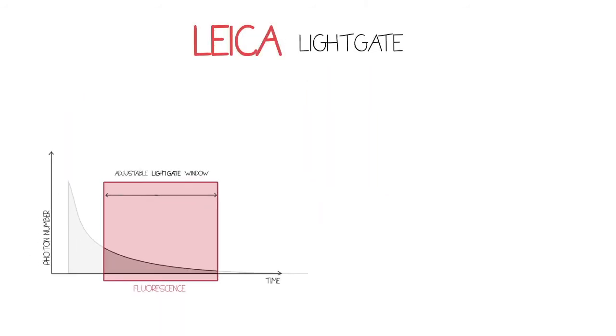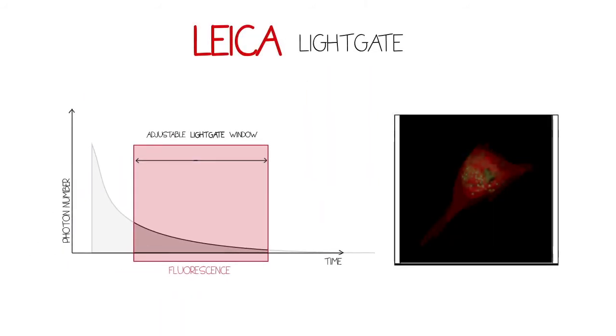With lightgate, STED laser intensity can be reduced without compromising resolution improvement. This allows for enhanced photostability, therefore facilitating live-cell super-resolution imaging.